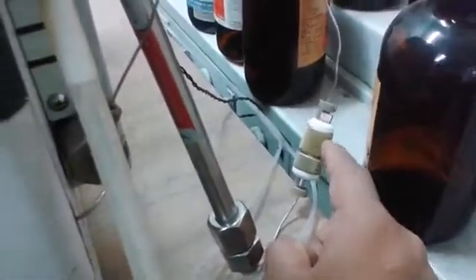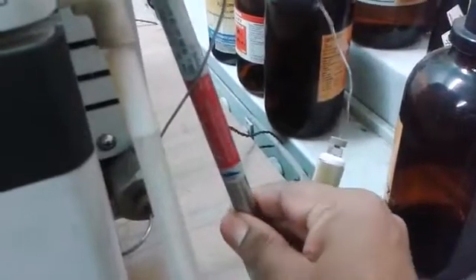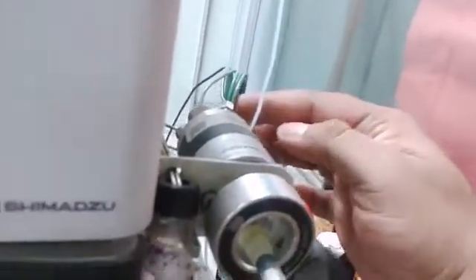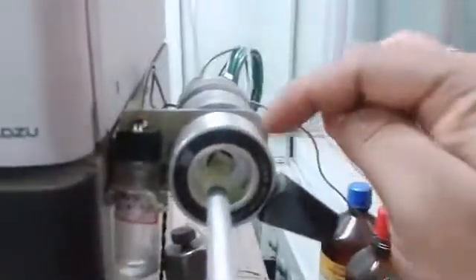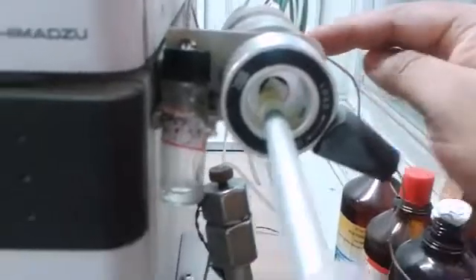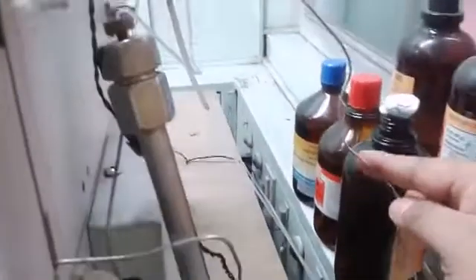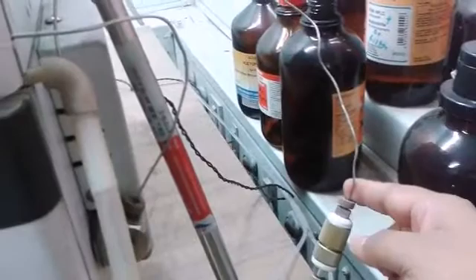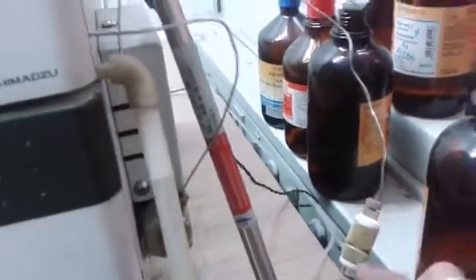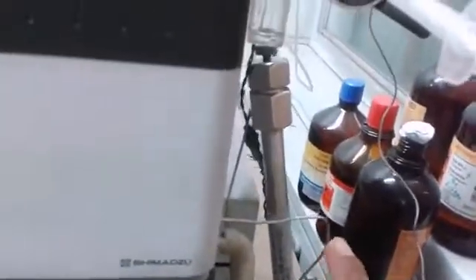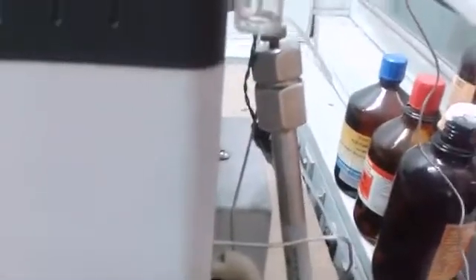And next is the guard column. This is the guard column. So put the guard column towards the arrow end. See, this is the arrow end flow. This goes to the injector inlet. So when you inject the sample, it will go from the injector through this pipe, then to the guard column, then it will enter the column. Any kind of dust particle or any other thing will just stop here.